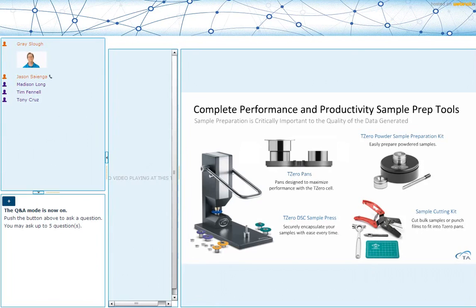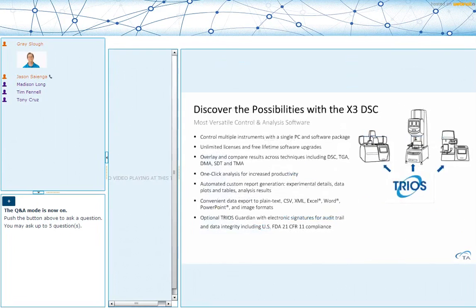But obviously, loading samples into pans and cutting and preparing samples is critical, to make sure that we maintain that efficiency in our production. So we have a sample prep toolkit that makes it very easy to load small quantities of powders into pans, as well as a new sample cutting kit that gives the ability to very easily punch out films, cut chunks of samples or cut squares. They're designed for the right size for the pans, and streamline the process of sample prep, so that we can spend more time examining the data and understanding the material, and less time in front of our prep station or in front of our DSC loading pans into our system.